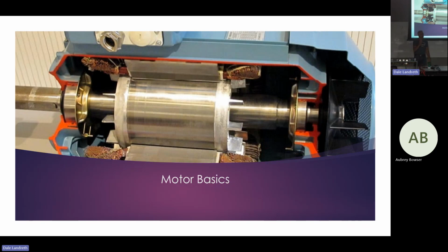Why do amps continue to go up when we only supply the same amount of voltage? If that makes any sense. Why would amps, if I were to take a discharge valve and shut it on a compressor, my amps are going to do what? They're going to go up immediately. Why do they keep going up? It's taking more force to turn that.